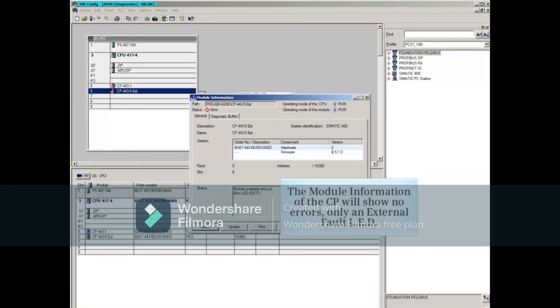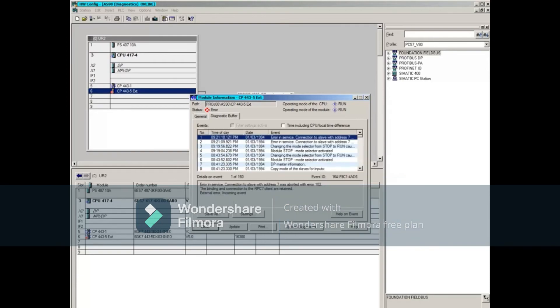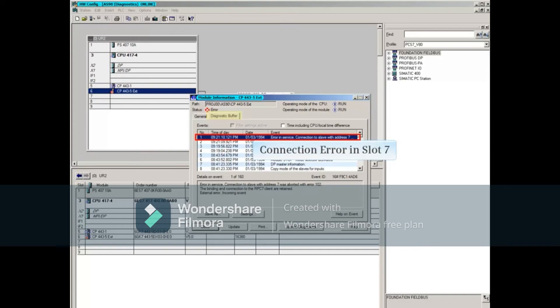The module information of the CP will, of course, show no errors, only an external fault LED. The diagnostic buffer, however, will show a connection error with the I.O. module in slot 7.